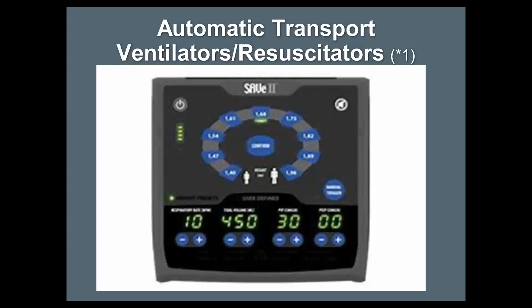So the vent needs to be supported. First off, I'm going to say securing the ventilator itself. It needs to be secure. Those portable ones are made to where a lot of times they can attach to a stretcher, underneath the stretcher, or close to the patient. I've actually secured them between the patient's legs, as long as the other hose had an adaptable oxygen source. A lot of these vents will not work otherwise. I've seen a lot of people want to tie them to just the Christmas tree that's on the regulator and turn it all the way up. You're going to have a lot of problems with that.